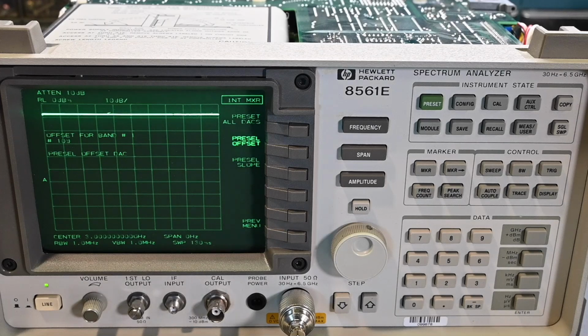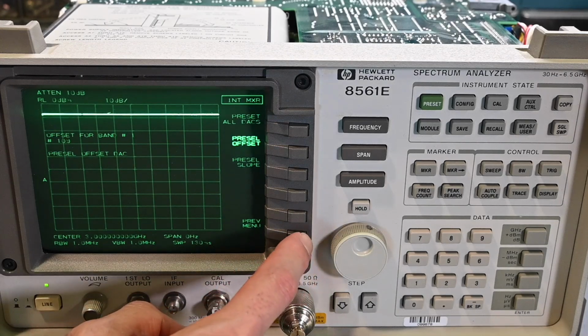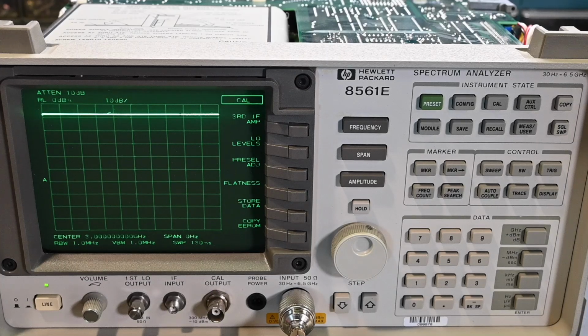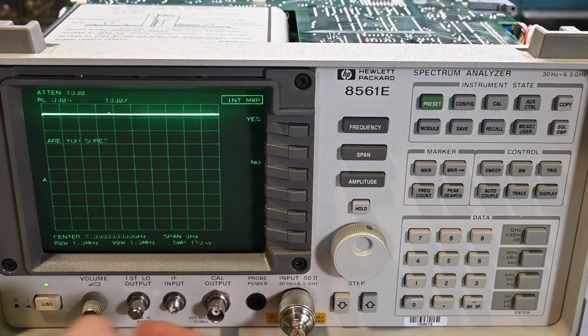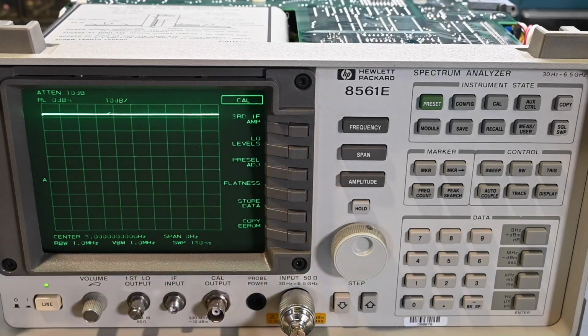So now the next step, it says, is to press the previous menu. So right here it says previous menu, so we'll do that. And then store data. So we have that right here, yep, store data. And yes. Okay, so data is stored. And then it says to place the write enable jumper back to the protection position. So I will reach around on the side of the instrument and do that. Okay, that is complete.